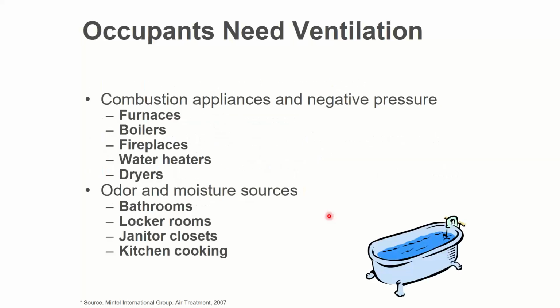We want to distinguish between combustion air and fresh air. Commercially, I think most of you get that. Residentially, it gets confused a lot. Like, I don't understand why I need a fresh air intake, I've got this two-pipe system for my boiler bringing the combustion air in that way. Dude, that has nothing to do with this. Combustion air is separate from ventilation air. So I need air coming into the building for combustion appliances, fuel-burning appliances that have exhaust; whatever they take out, I've got to make it back up. And then I also need fresh air for the occupants themselves.